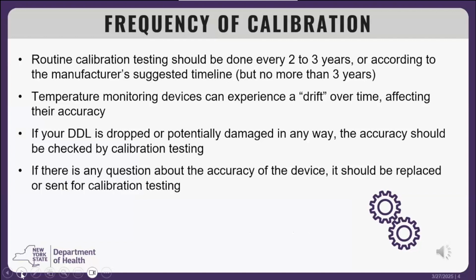Temperature monitoring devices can experience a drift over time, impacting their accuracy. This testing ensures the accuracy of the device continues to conform to nationally accepted standards. Mishandling a DDL can impact its accuracy. If your DDL is dropped or potentially damaged in any way, its accuracy should be checked against another calibrated DDL. If there is any question about the accuracy of the device, it should be replaced or sent for calibration testing.